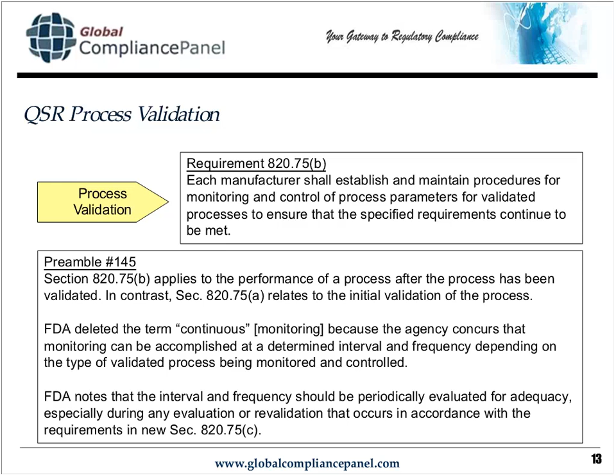Initially, FDA said the parameters had to be continuously monitored, and comments pointed out that you can't always do that—maybe you don't have a data logger. Maybe you just check the input parameters every so often and record what they are, and as long as they stay in control, you're fine. So the issue here is that we're going to monitor the input parameters at some predetermined interval and frequency, and that gives us enough information to know that the input parameters stay inside the acceptable range.